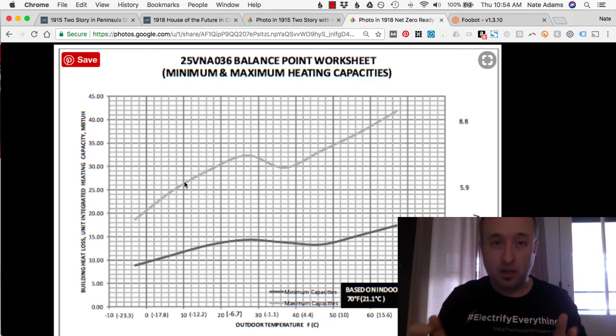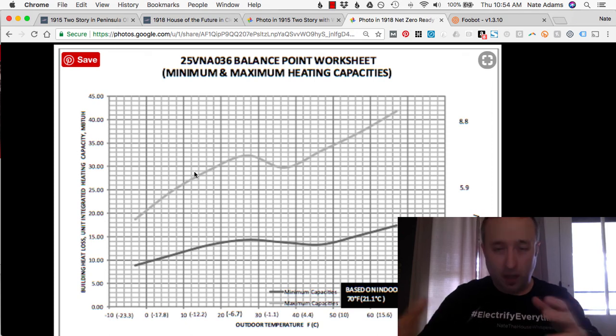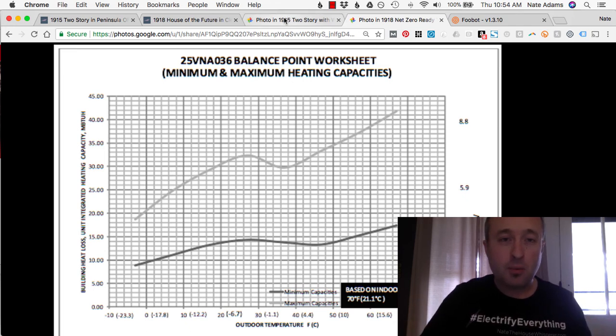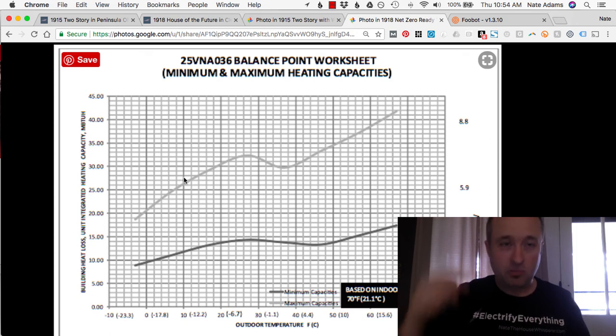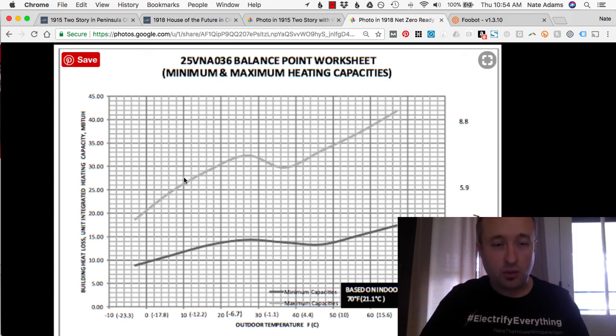They're not perfect, they just help us narrow the band so we can make really good educated guesses instead of wild guesses. Looking at this, I know the house loses the war somewhere around 10 degrees, and the unit is putting out about 27,000 BTUs, so this house uses about 27,000 BTUs to heat it at 10 degrees. That matches up pretty closely with the load calculation, which was about 27,000 between the first and second floor. So it gives you an idea of what's going on.